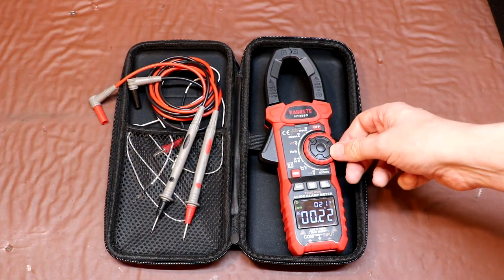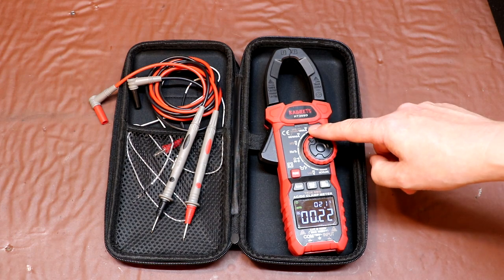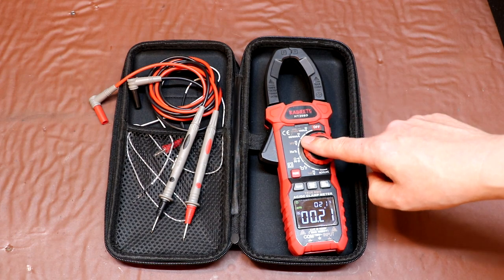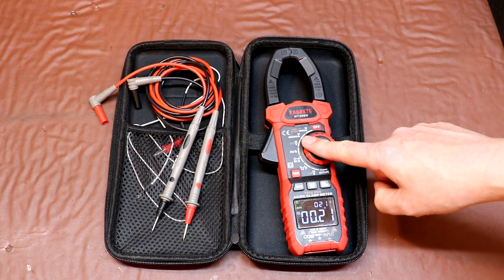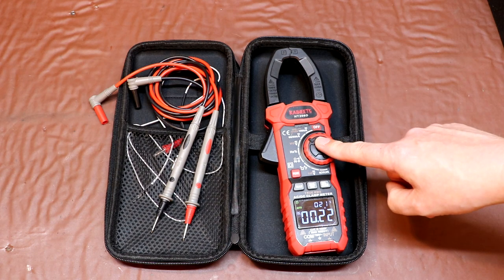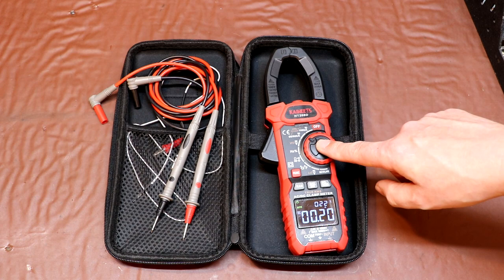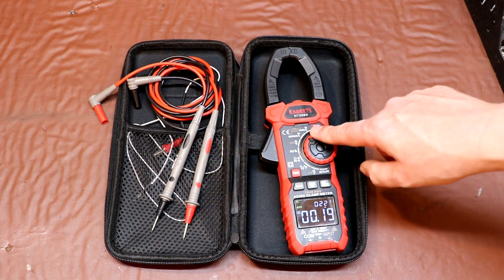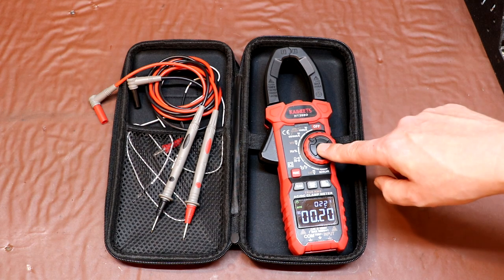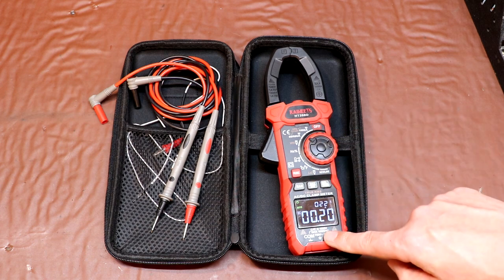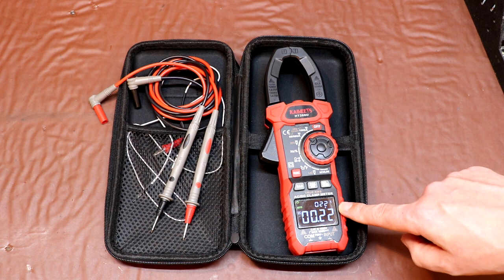Based on the testing that I could do, I thought that both the 1000 amp and the 600 amp AC and DC current ranges did appear to be very accurate. I did find one problem with both the 600 amp and the 1000 amp ranges which really concerned me, and that is if you've got a voltage source connected to the meter, it actually affects the current measurement range.